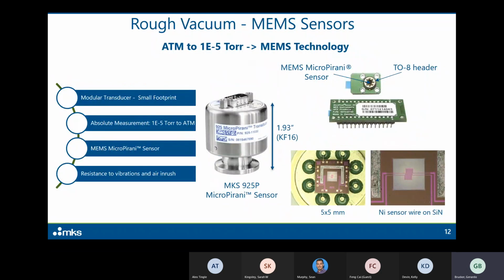When we started with the 900 series, the first thing that we did was focus on rough vacuum measurements, anywhere from atmosphere to 10⁻⁵ torr, and we were able to take care of MEMS technology sensors at that point. So here's a perfect example of the very first 900 series product that we released. This is the 925. This is a modular transducer again, right? So apply power, bring the gas in, and then a signal comes out. So we transduce pressure into a voltage or pressure into a digital signal. In a very, very small footprint, you can actually see this guy is pretty small, 1.93 inches for a KF16 flange. It's capable of measuring pressure from 10⁻⁵ torr to atmosphere.